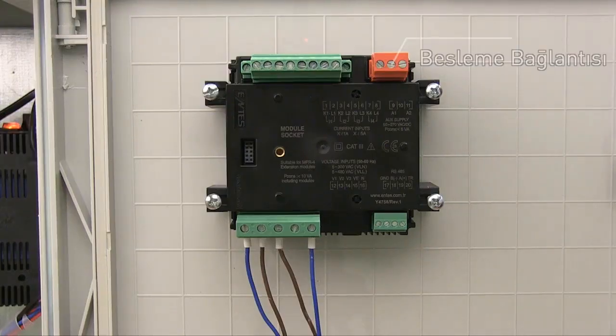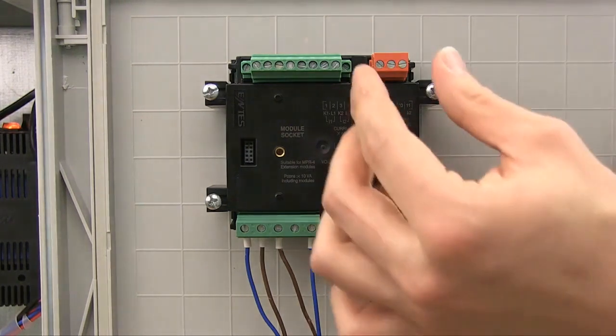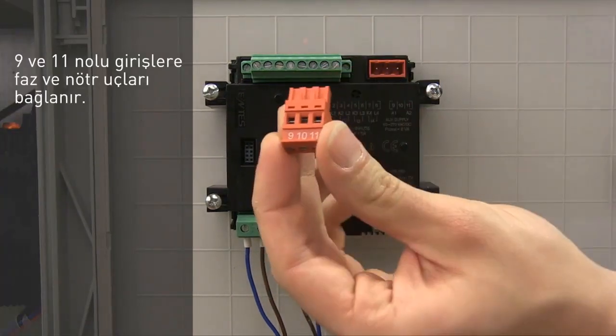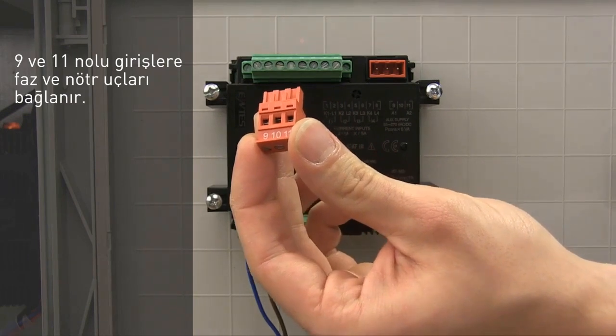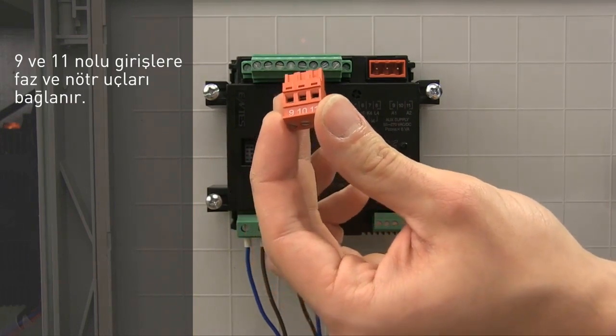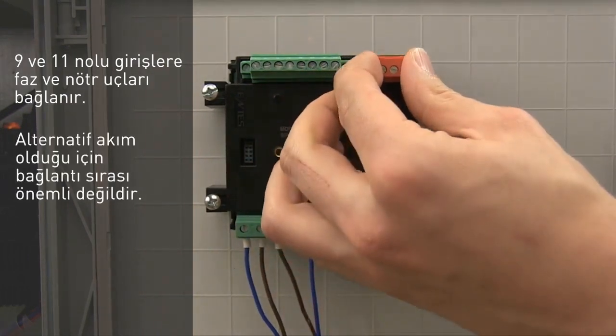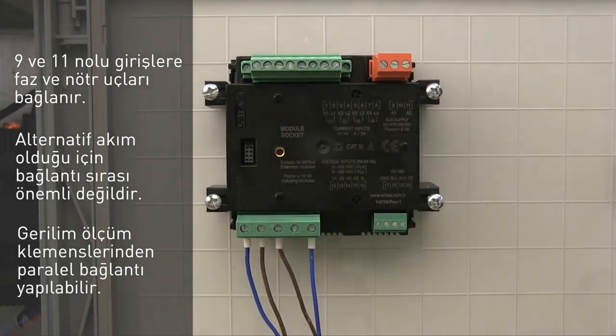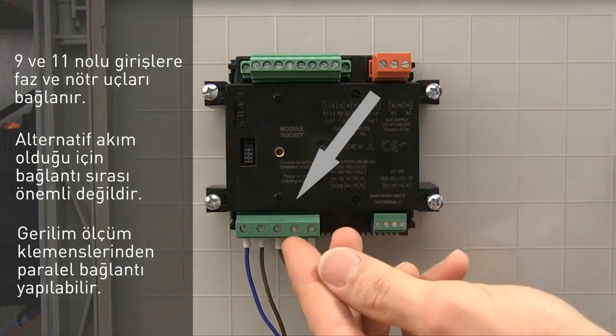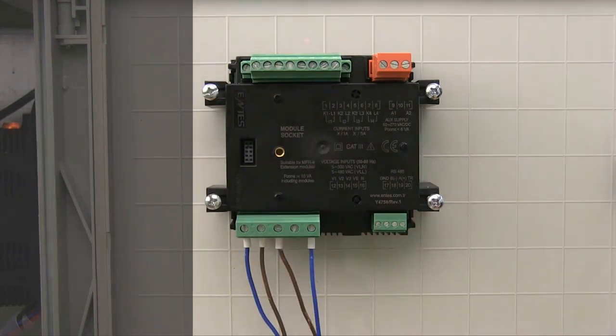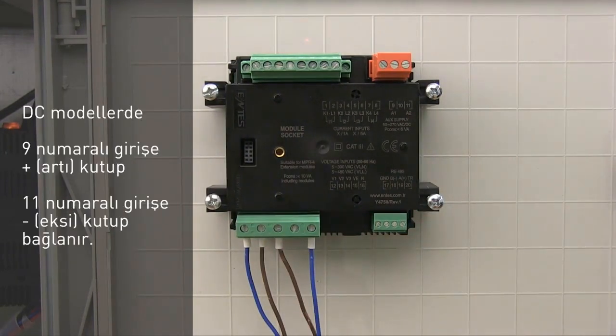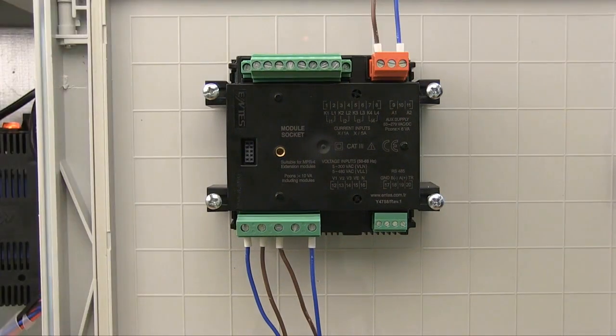Secondly, power connections of the device need to be made. The supply terminals located at the top right corner of the device have the number 9 and 11 inputs, where the live and neutral leads from the grid are connected. For AC, the order is irrelevant. For DC, positive goes to 9, negative to 11. You can preferably make a parallel connection from the voltage measurement terminals. In DC models, it's important to connect the positive terminal to input number 9 and the negative terminal to input number 11.